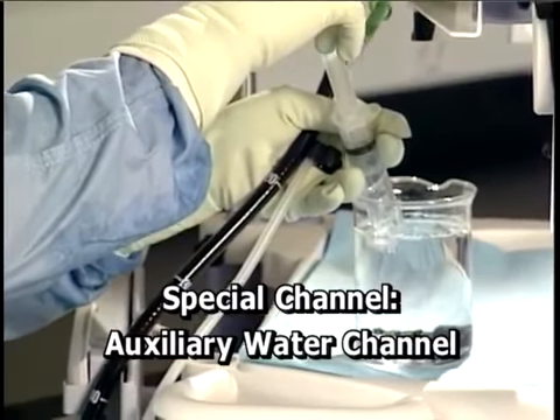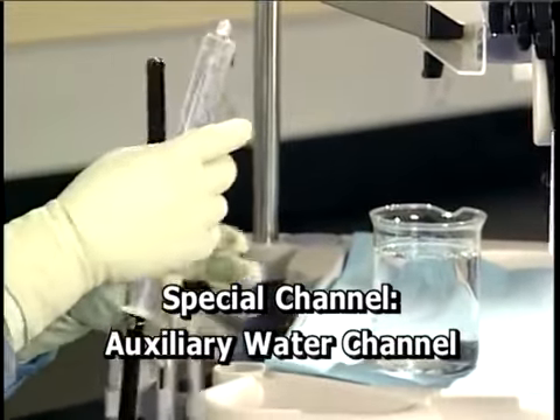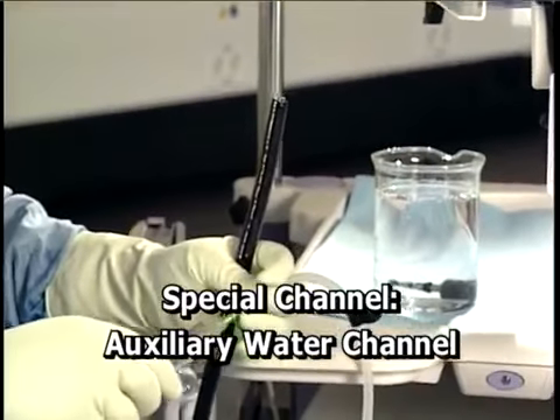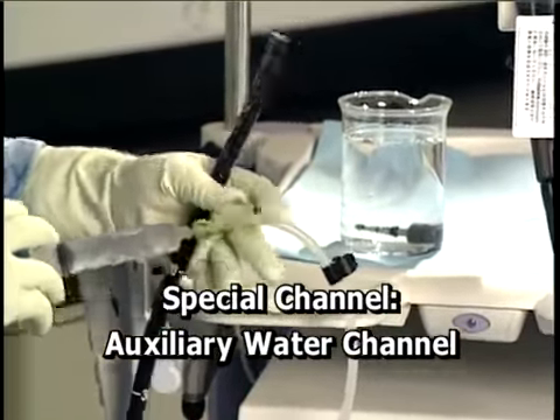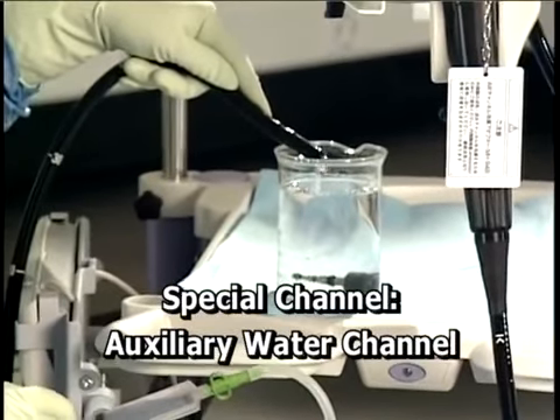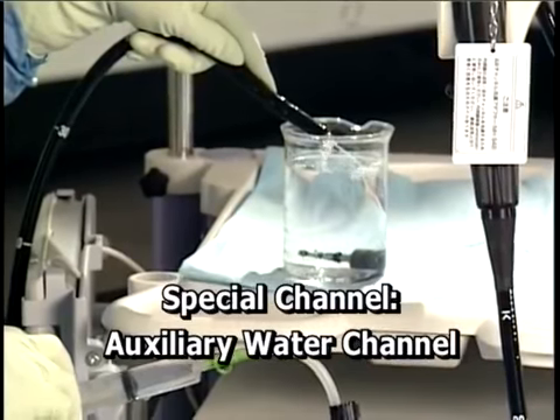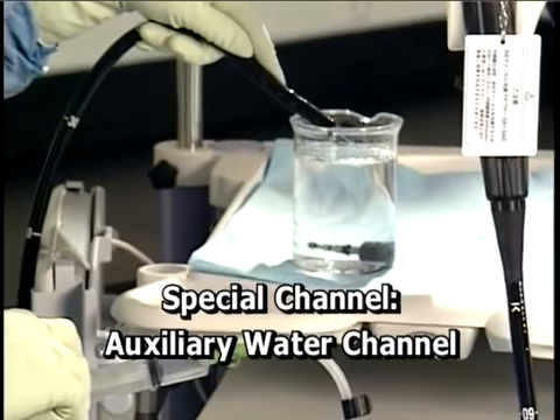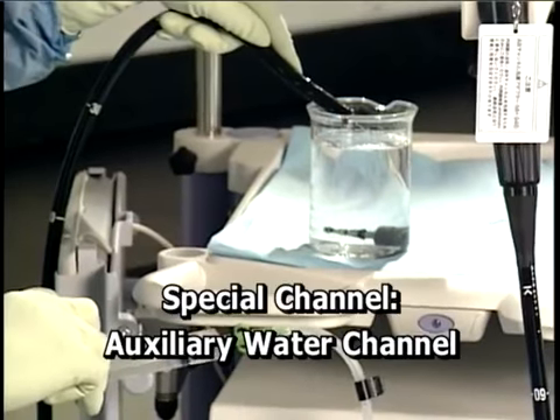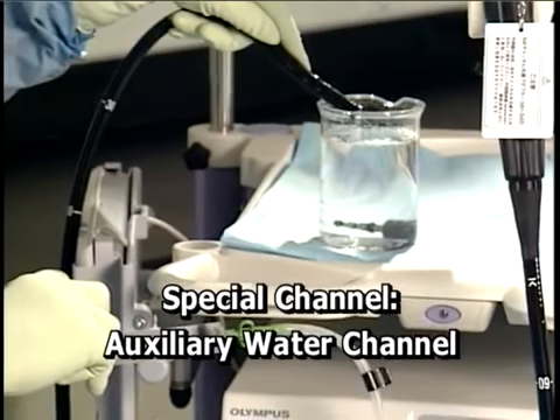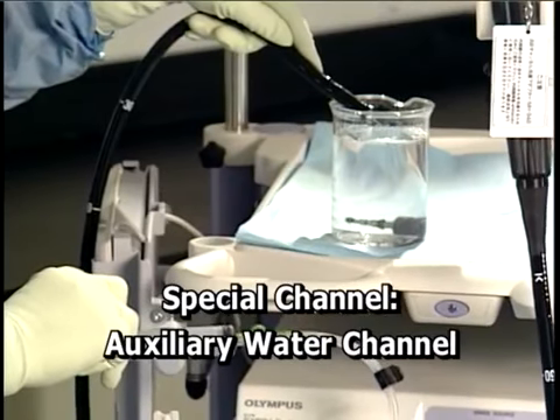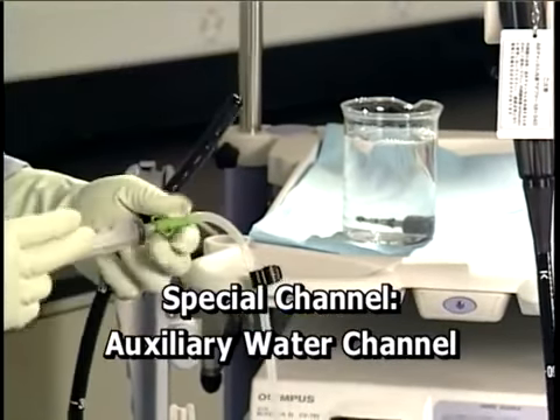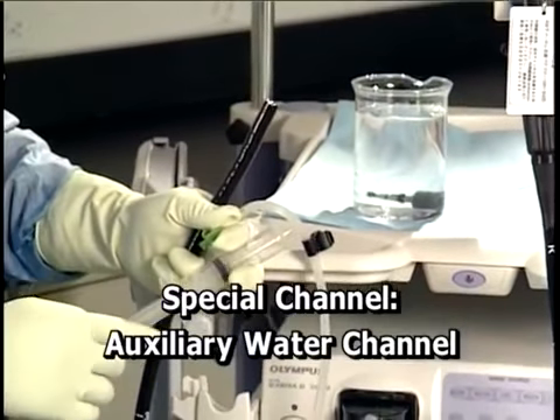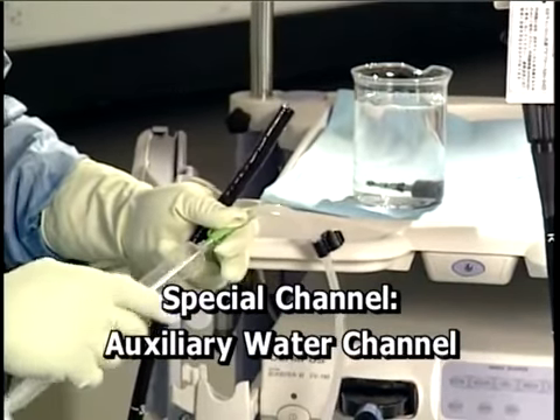If your endoscope has an auxiliary water channel, connect an injection tube to the auxiliary water connector and flush detergent through this channel. Expel this detergent by flushing with air.